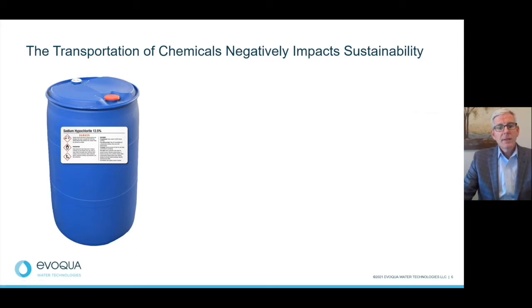Now, this biocide is referred to as an oxidizing biocide, and it is a very effective biocide. In fact, the Cooling Tower Institute recommends maintaining a residual of oxidizing biocide in your cooling water, just like you might do in a swimming pool. This is to reduce the risks associated with bacteria and biofilms, most notably Legionnaires' disease.